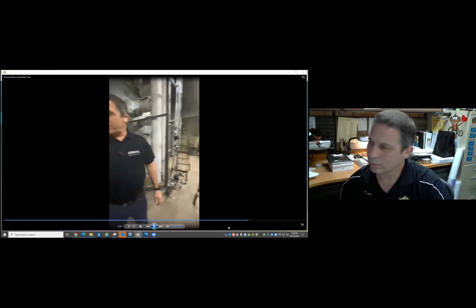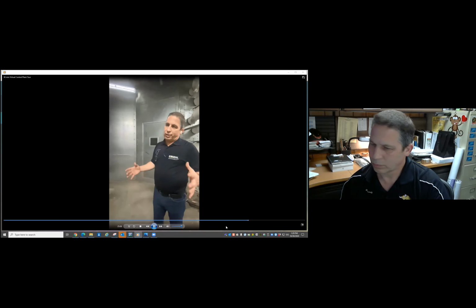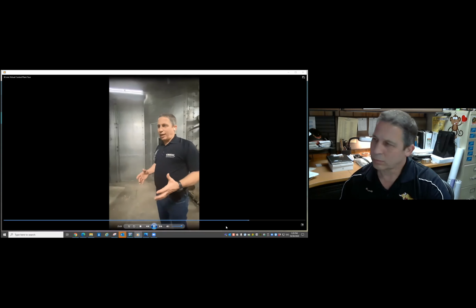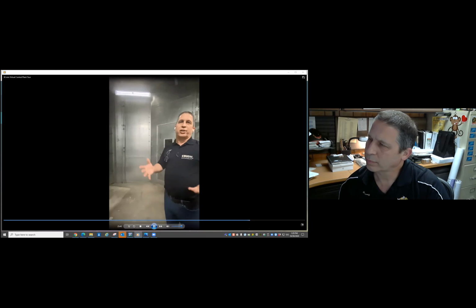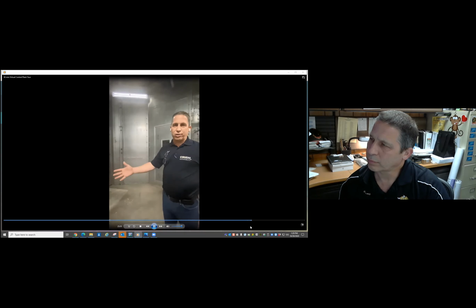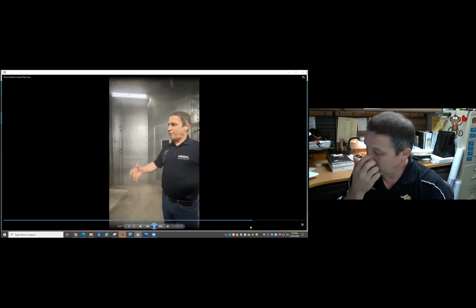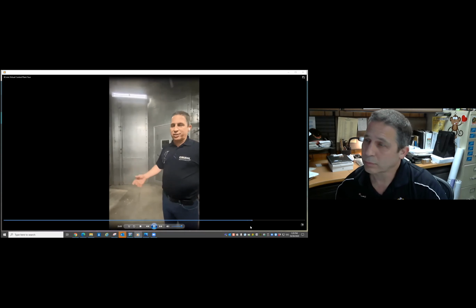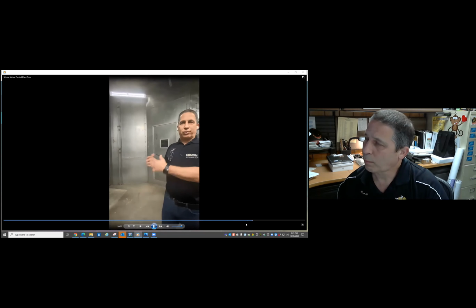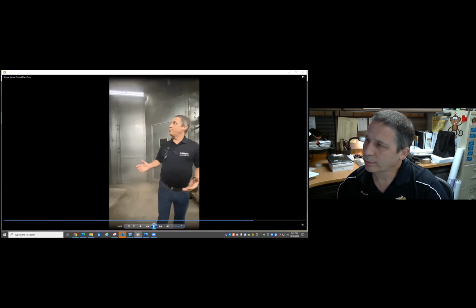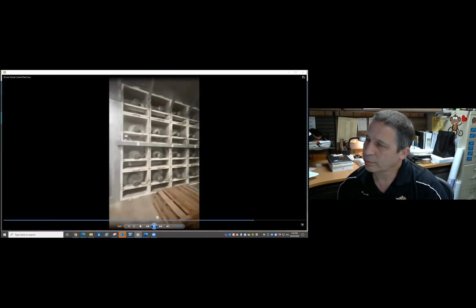The beauty of the fan walls is that if you remember, like Big Bertha or the one we looked at for the library, if that fan motor breaks, the whole building section is offline, and it's heavy and takes time to get a 100 horsepower motor. Instead here we have just a bunch of little 7 horsepower motors, and if one of these were to fail, we'd have plenty of time to order a new one, get it in place, and change it out without shutting the building down. Much more efficient.